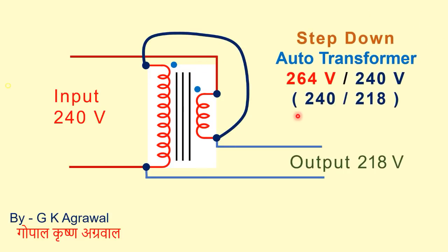Now, this has become step down auto transformer 264 by 240 volt or 240 by 218 volt. Here I have made only one extra connection, this one. Here we can give 240 volt input, here we will get 218 volt output. There will not be any isolation between primary and secondary. Here voltage is more because this winding turns are added to this winding turn in the primary. This dot indicates the polarity of this winding, this dot indicates the polarity of this winding.